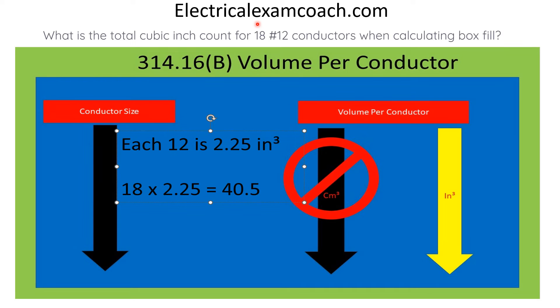To find this answer, we head to 314.16(b). We start on the left-hand side and find our size conductor. Then we come all the way over to the cubic inches column and select our individual conductor value. Each 12-gauge conductor is 2.25 cubic inches. We take our 18 conductors, multiply by 2.25 cubic inches, and we end up with 40.5 cubic inches.